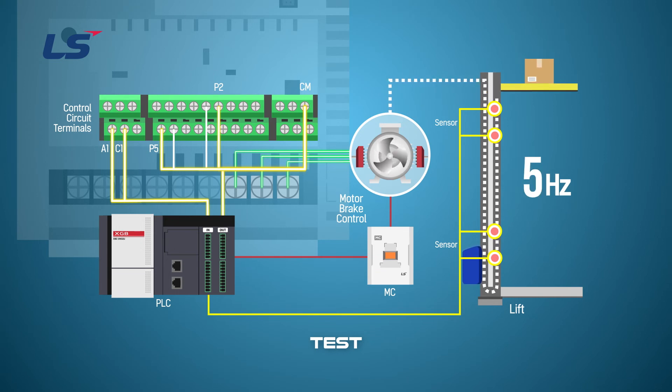When the lift passes the sensor at the top, it changes from the P5 signal to the P6 signal and it descends at 15 Hz. When it passes through the lower sensor again, the P6 terminal turns off and the P5 terminal operates and is set to 5 Hz.